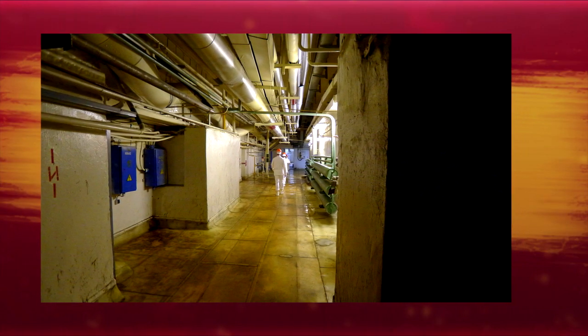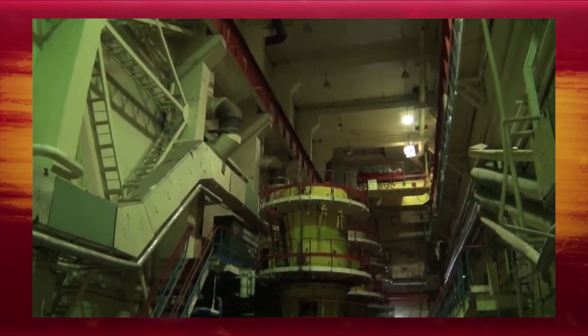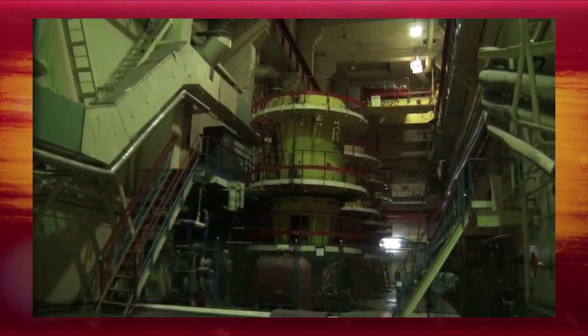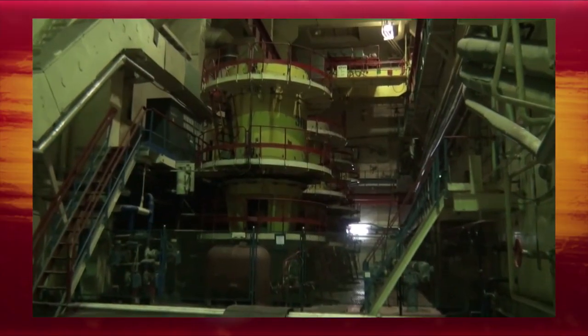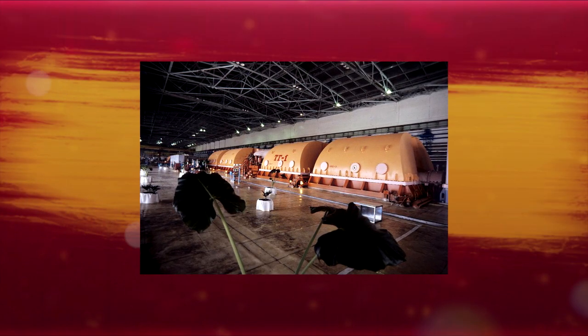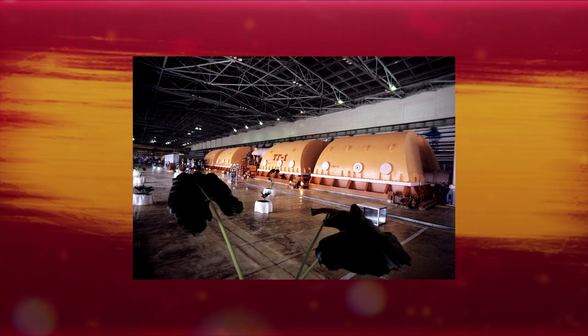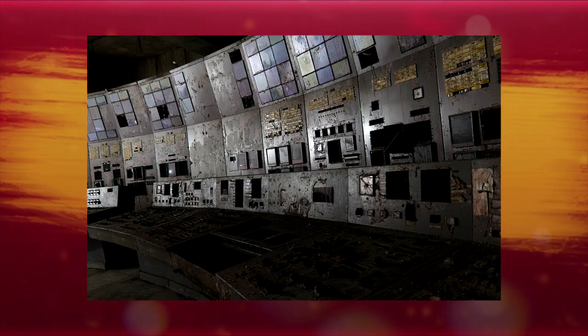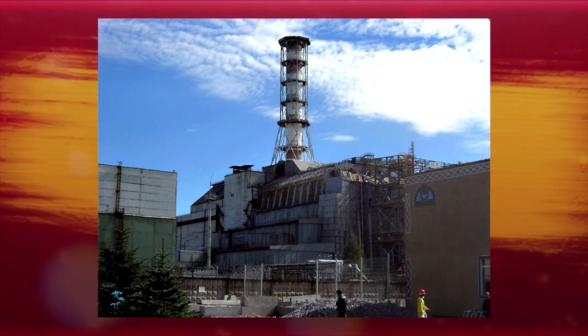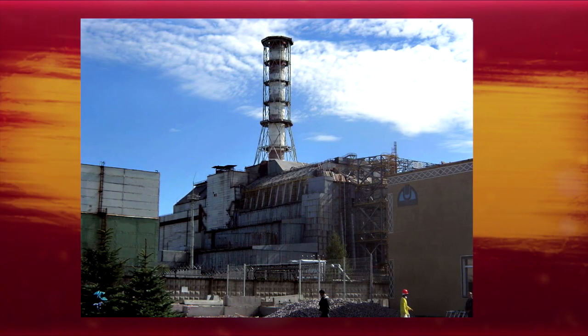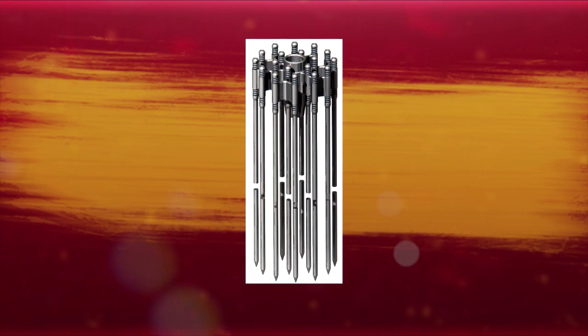Before a standard shutdown procedure, the reactor crew at Chernobyl 4 were preparing for a test, which would measure how long turbines would spin and supply power to the main circulating pumps if power from the main electrical supply was lost. The test had been carried out once before the previous year, but the power from the turbine was lost too quickly, so another test with new voltage regulators had to be completed. A series of operator actions, including but not limited to the disabling of automatic shutdown mechanisms, left the reactor in an extremely unstable condition. As the control rods were inserted into the reactor, a dramatic surge of power was caused.